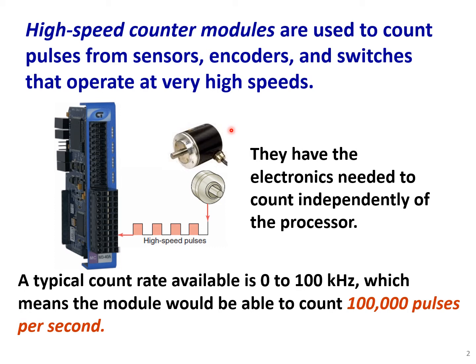It could be an optical encoder or a magnetic encoder. In most cases, they are optical encoders for high accuracy, either relative or absolute. We have a huge amount of data coming at a high rate, and that's why we use this type of special input device. These input devices are capable of accepting, reading, and translating the data for the PLC.